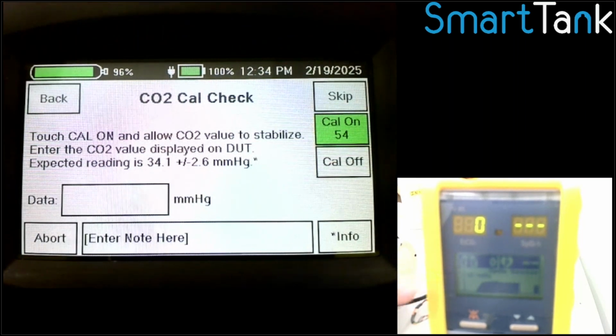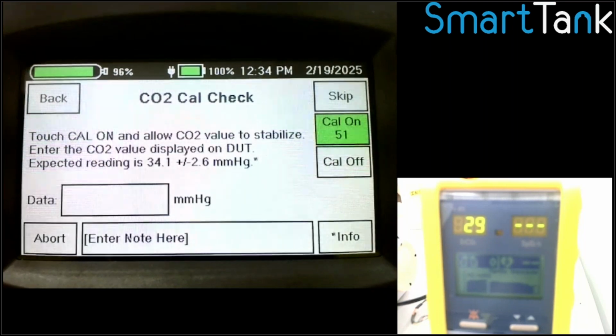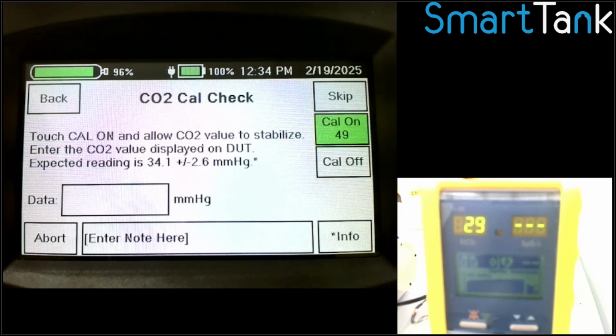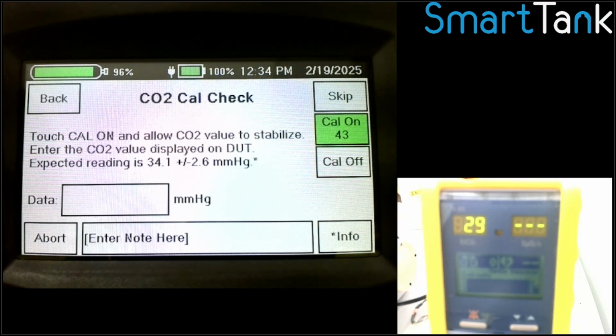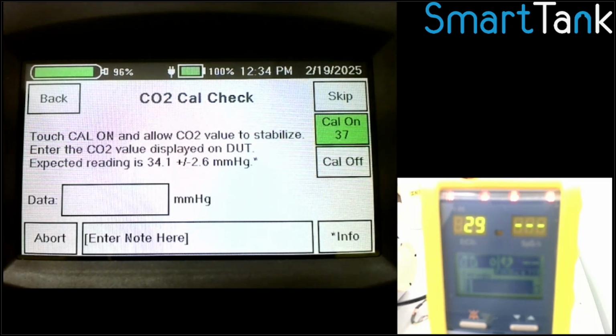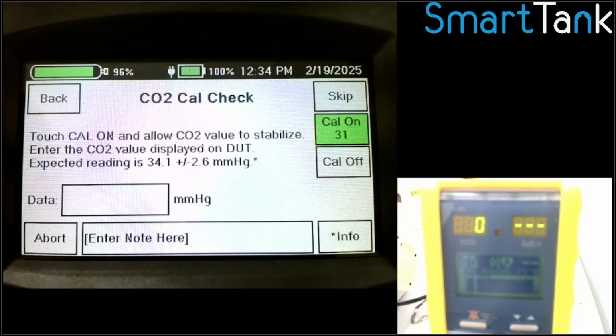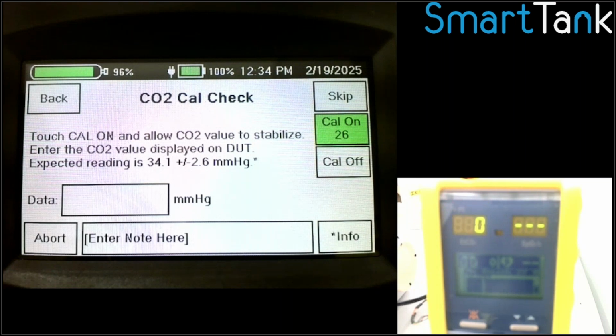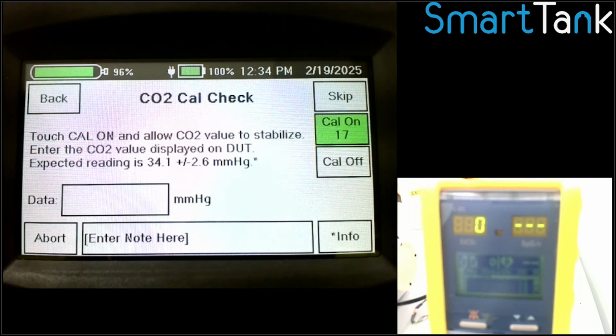So one of the things we heard from everybody we talked to is, can you save us gas? We use way too much gas, it's expensive. And so we really designed the SmartTank to use as little gas as possible. In reality, we use the flow meter inside to measure how much gas the device needs and to deliver just a little bit more. If you remember, we measured the flow at about 45 milliliters a minute, so we're giving it about 46, 47 milliliters a minute. If you use a regulator and crack it, you're using 200 to 300 milliliters a minute minimum. There's no real way to not use that much gas. So this is using a sixth of the gas.